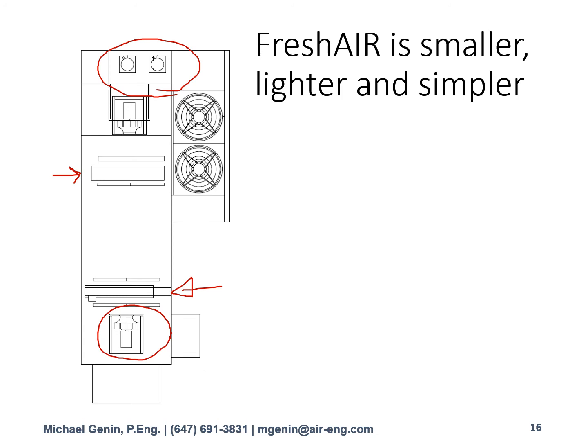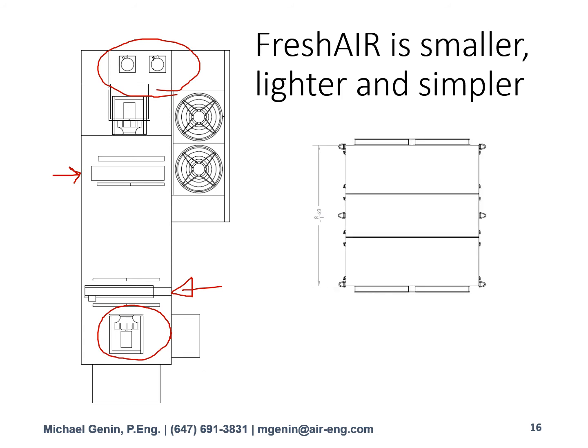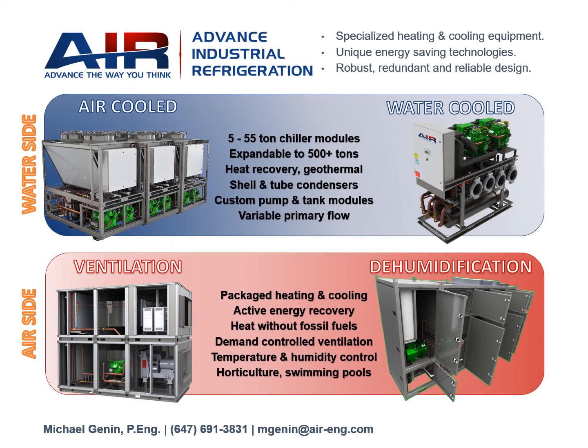It's sized for a certain CFM, and we sized a fresh air unit for the same amount of CFM, the same amount of cooling, and the same amount of heating. And there is the footprint of the fresh air unit. It is less than half the footprint of a traditional heat recovery unit. That's another great example of how it can benefit and fit in tight installations, so you can recover energy from places that previously were not feasible. And that concludes the webinar.